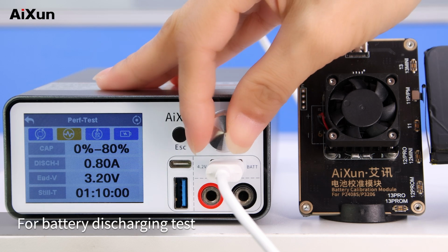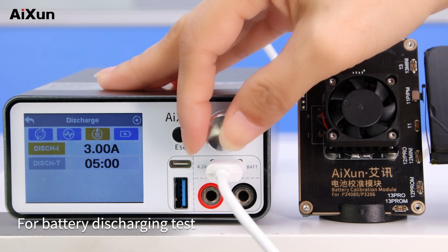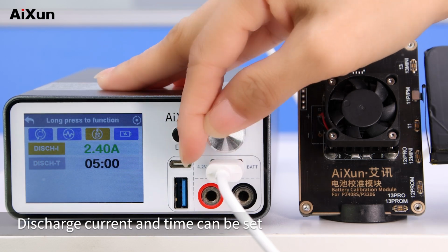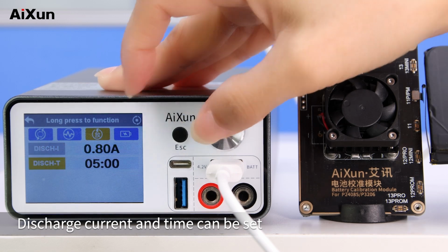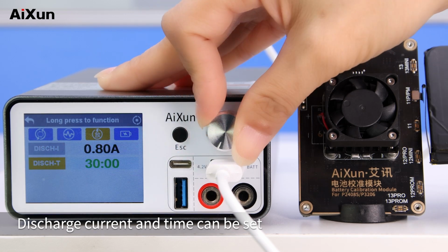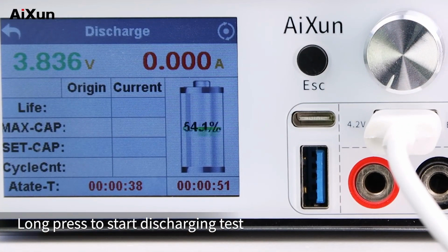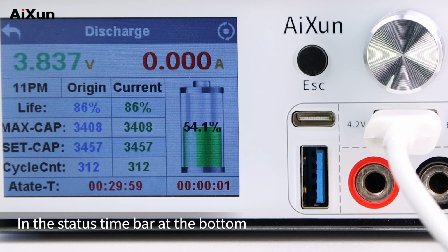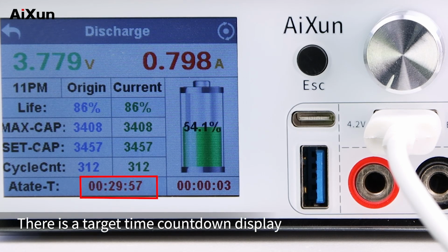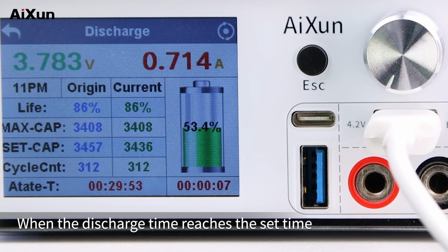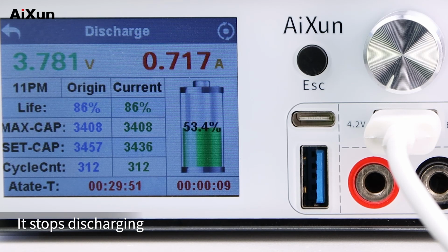Discharging test. For battery discharging test, discharge current and time can be set. Long press to start discharging test. In the status time bar at the bottom, there is a target time countdown display. When the discharge time reaches the set time, it stops discharging.